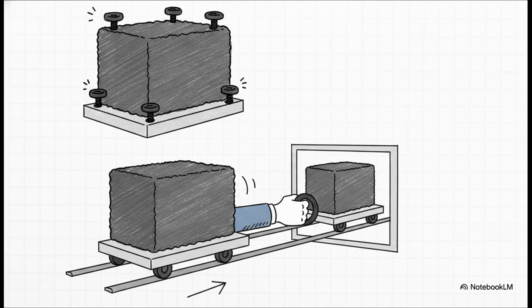On marine medium voltage switchboards, these are heavily resin insulated, and when it comes to how they're physically mounted inside the cabinet, you'll generally encounter two styles. First, they can just be bolted and fixed permanently in place. Or, and honestly, this is a brilliant feature for shipboard maintenance, they can be mounted on a withdrawable truck, kind of like how the main circuit breaker itself is mounted. This is a big deal because it means the technician can physically rack out and pull the VT for inspection or maintenance without having to completely shut down and de-energize the entire board.